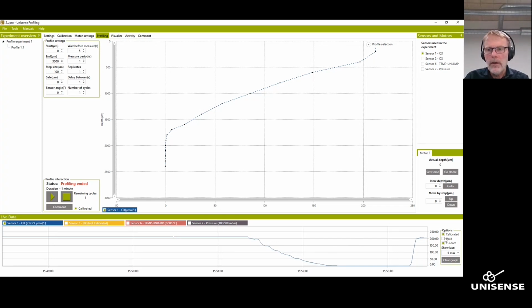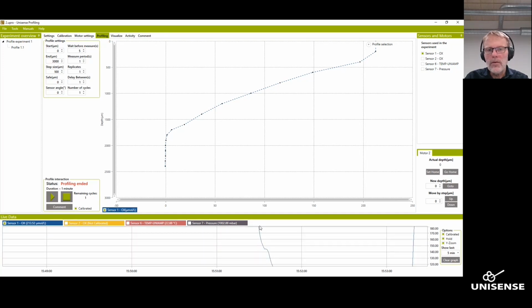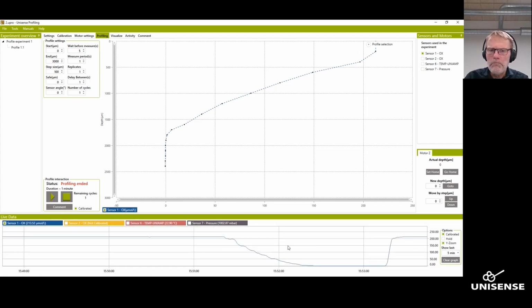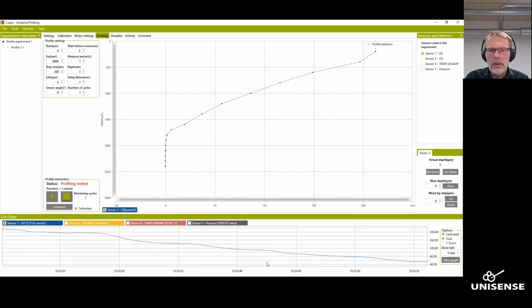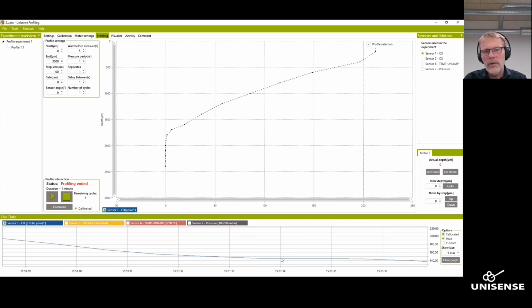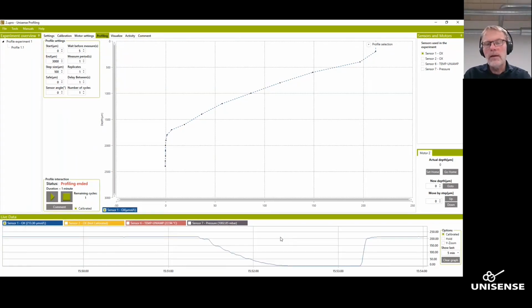And you can see down here now, if I click hold, then we can see it a bit more closely on the data. You can see it's going sort of in steps down. And if you look at one of these steps, you'll like to see that it actually becomes stable before it moves on. It does more or less. If we just click the Y zoom away, I can just go in and have a look at these. So you see, well, it's almost stable, but for a good profile it's quite okay. It's quite flat here. So it has stabilized before it took the measurement. So the measurements should actually be good. You can also zoom in on this data as you are measuring, and you can change the wait before measure if you discover that you have chosen a too short or too long period.